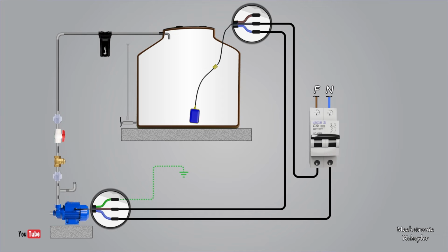In this way, when you raise the lever of the key or manual switch, and the float is at the minimum level, then it should allow you to turn on the electric pump to fill the tank. And if it reaches the maximum level, then it should allow the circuit to be disconnected automatically and the electric pump to be turned off.